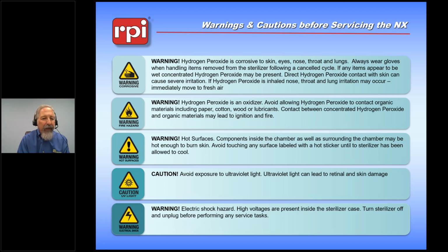This is a list of warnings that everyone who touches this machine or has worked under the cabinet should be aware of. One in particular that I might point out is that when you open the door of the peroxide sterilizer at the end of the run, there is still a possibility there might be some small amount of hydrogen peroxide left within the chamber. You just don't want to put your nose directly in front of the door when you open it. Just make sure that you let the air within the chamber dissipate a little bit before you pull the material out.